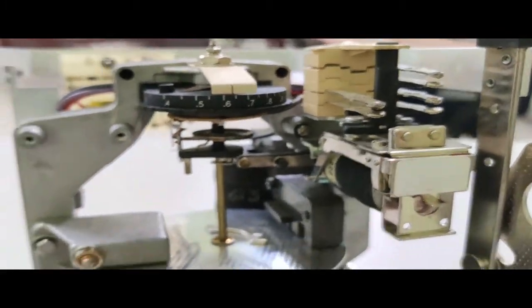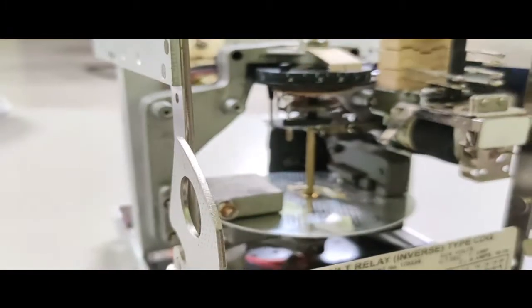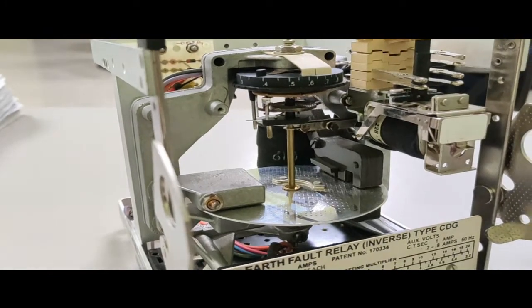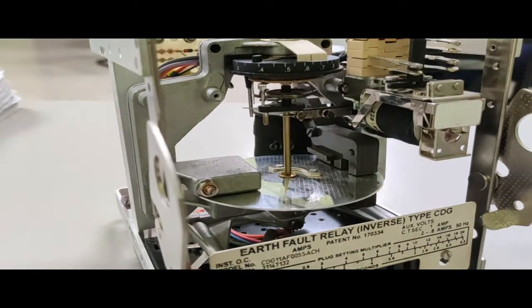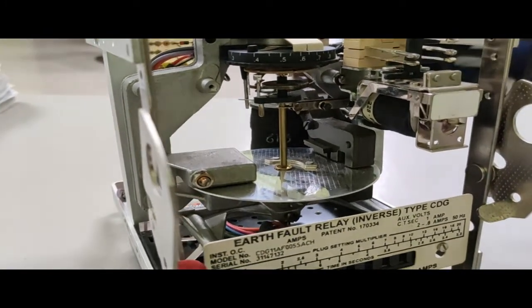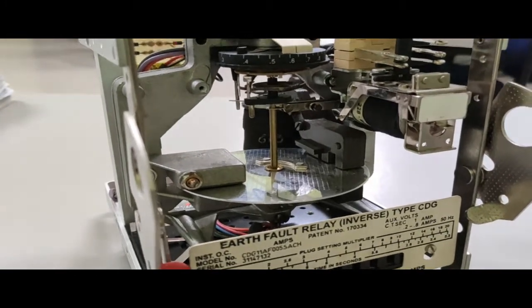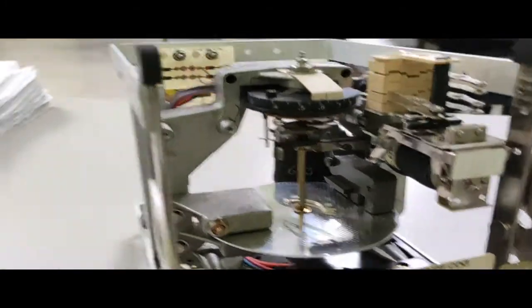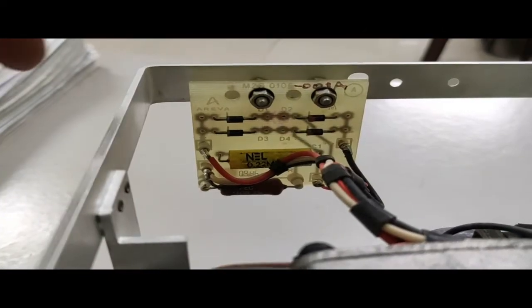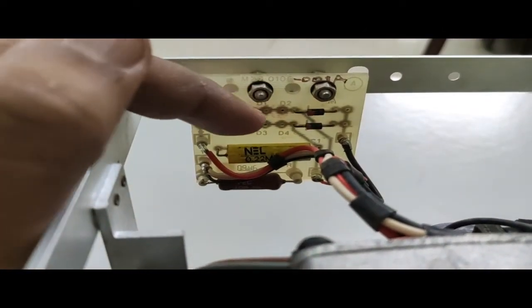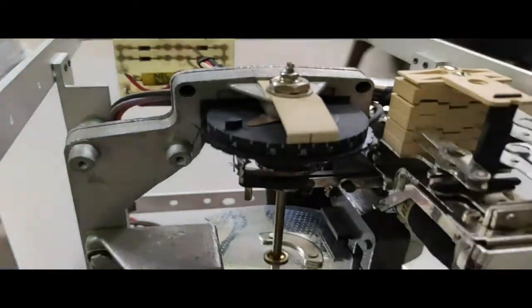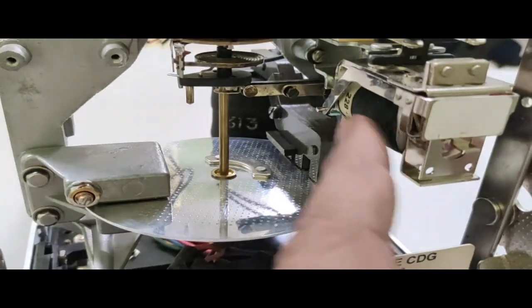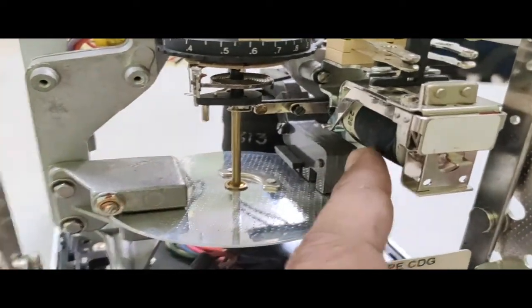So in this way the relay operates. Now that means inside a relay two coils are there. One is the relay coil, another is the tripping coil of the relay. The relay coil is operated on AC, but the tripping coil is operated on DC to make always a unidirectional force. So how is the DC produced? Here you see one rectifier is there. Using this bridge rectifier, the AC is converted to DC, and this DC is supplied here. So this is the tripping coil of the relay.